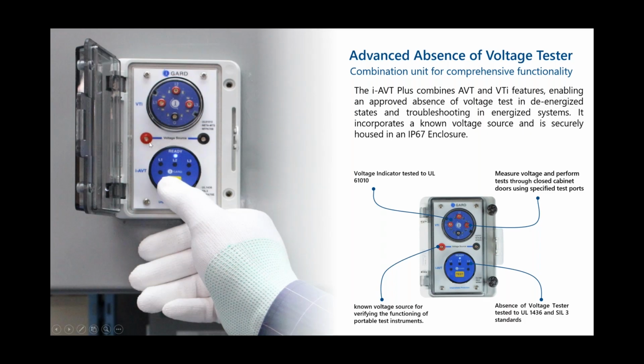rating. In addition to that, for when we're using a multimeter and online voltage testing, we've also put a known voltage source so that they can confirm that their multimeter is properly calibrated and is working as it should. So this is a combined unit, and we feel like there's an advantage both for online voltage testing and offline voltage testing with this product. In the future, we plan on getting a higher voltage unit for this, for both the voltage test ports as well as the absence of voltage tester, so that we can create a safer environment and reduce the electrical shock and fatalities that have been occurring throughout the years in the past.